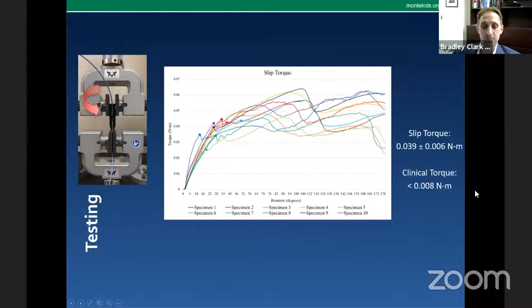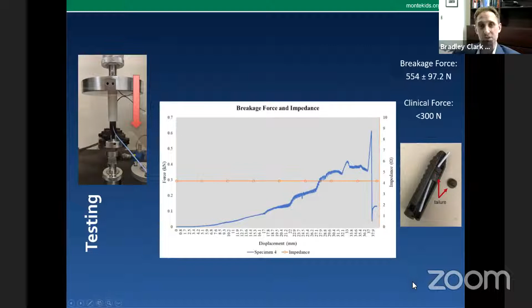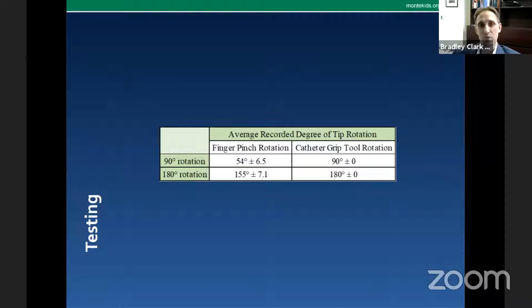Slip torque testing showed an average slip torque 5 times greater than the torque exhibited when you rotate a catheter inside a blood vessel. Maximum grip strength testing showed tool failure at nearly 2 times the maximum force that a human being can generate. And finally, simulated use testing showed superior catheter rotation at both 90 and 180 degrees with PeriTorque compared with manual manipulation alone.